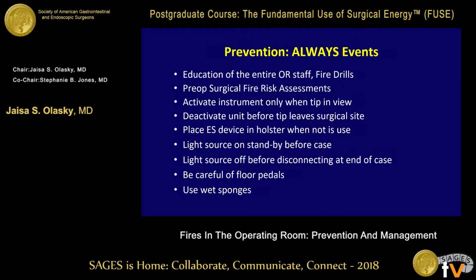And then when we talk about electrosurgery as being an increased risk for these OR fires, we want to make sure to activate the instrument only when the tip is in view. Make sure that when we're moving the instrument out of our view, we've deactivated it, knowing where your foot pedals are at all times. Because if someone steps on the foot pedal, maybe in this case it might not cause a burn right away, but you could go on to ignite a fire if you don't know where that energy is going. And having your light source on standby before the case and then turning it off as soon as you're done with the laparoscopic portion of the case.